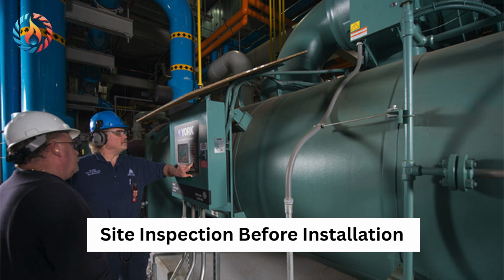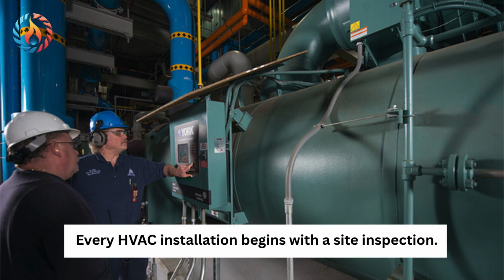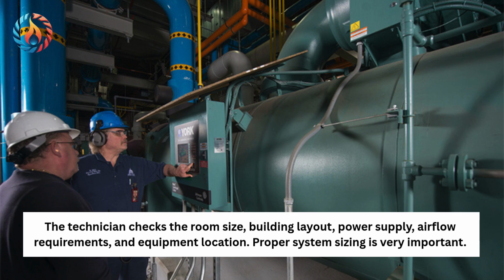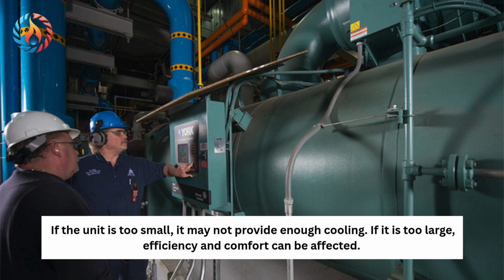Site inspection before installation. Every HVAC installation begins with a site inspection. The technician checks the room size, building layout, power supply, airflow requirements, and equipment location. Proper system sizing is very important. If the unit is too small, it may not provide enough cooling. If it is too large, efficiency and comfort can be affected.